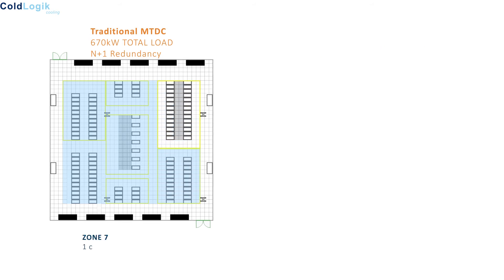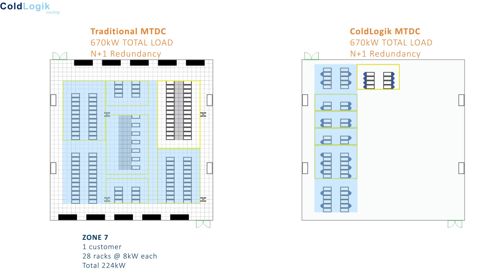This final group of racks are enclosed in a fixed aisle containment setup, enabling a higher duty of 8 kW per rack. But the commitment to aisle containment and its restrictive nature is highlighted again. The critical difference is that ColdLogik RDC allows expansion one rack at a time if necessary, rather than a full commitment — in this case a 28-rack pod. The irony is that many installed pods have racks which are fully blanked up, or worse still rack-sized infill panels, waiting for racks to be installed. Installed the ColdLogik way, zone 7 could be reduced to 8 racks each at 28 kW, down from 28 racks.